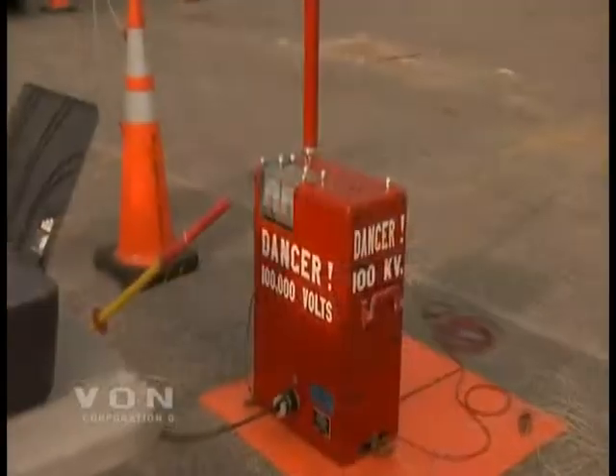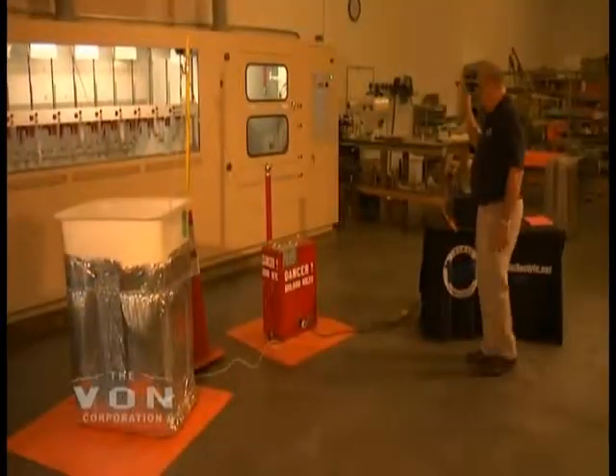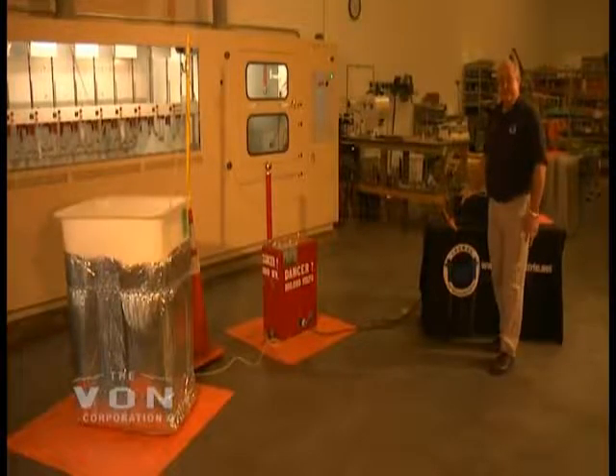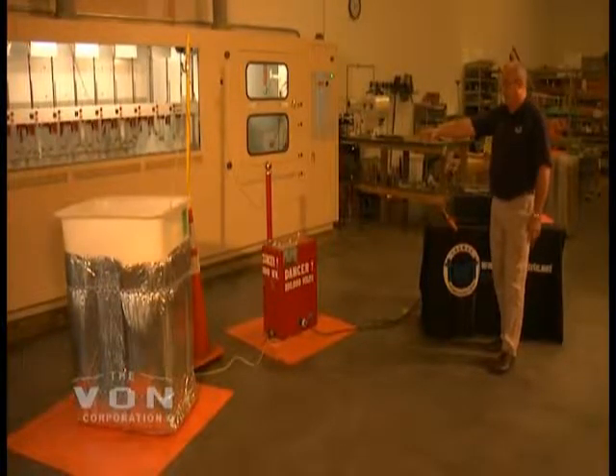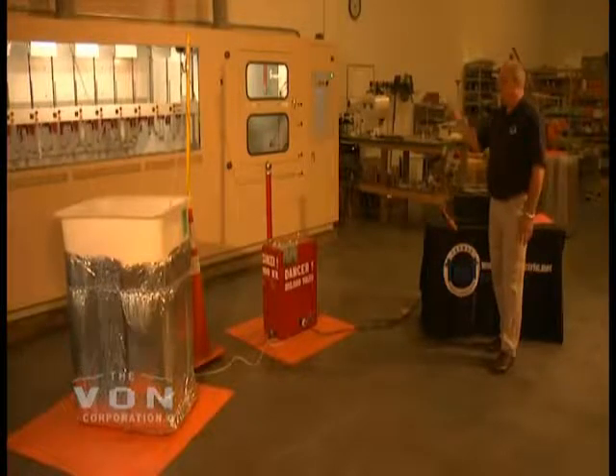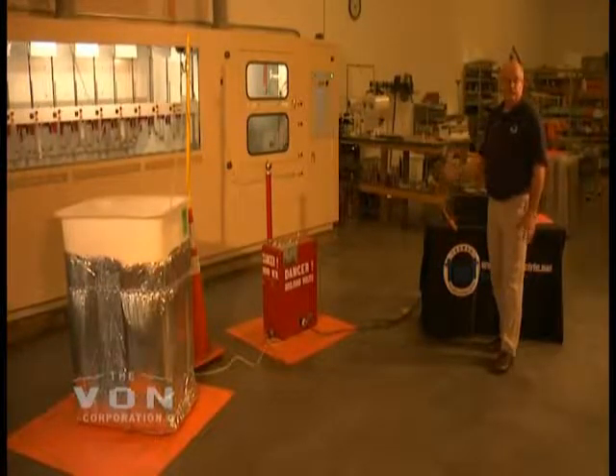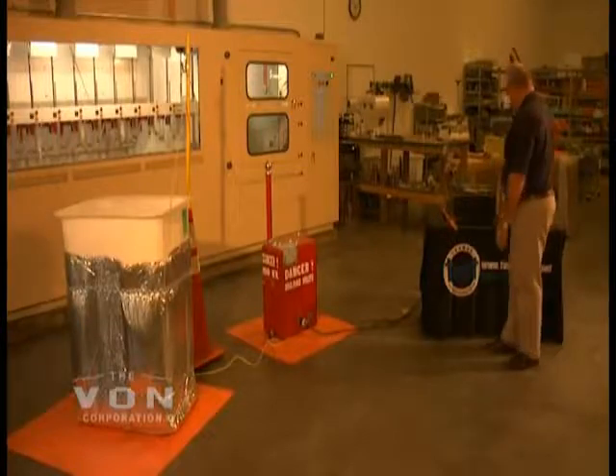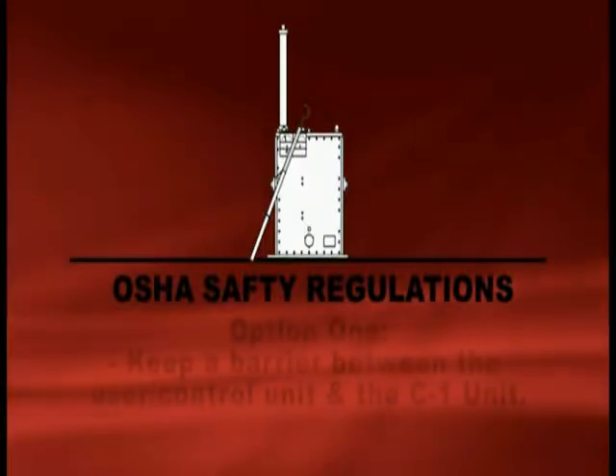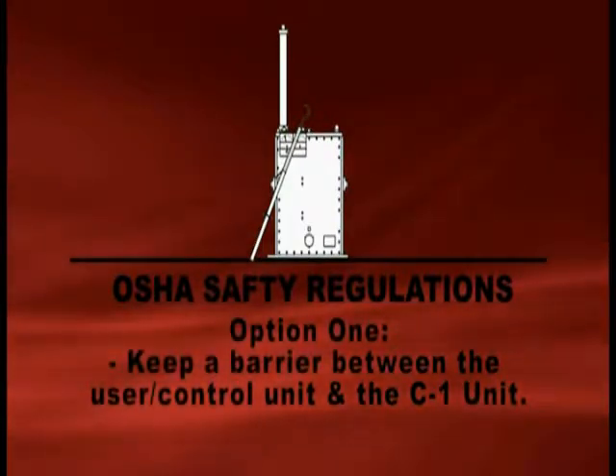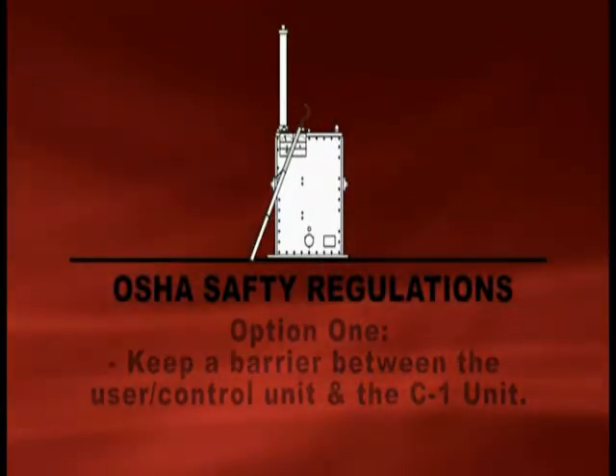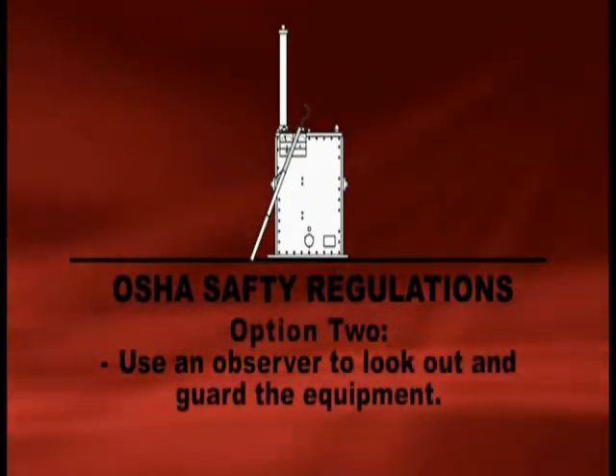Always ensure that your control unit is at least 18 inches away from your high voltage box. That way that ensures if anybody points at it, then their fingers will stay at least 18 inches away from the high voltage leads. In field testing of bucket trucks and digger derrick trucks, OSHA requires that you keep a barrier between the control unit and the person controlling in the high voltage red box. There is also a second option that you can have an observer that will make sure that people stay away from the high voltage leads and the high voltage box.